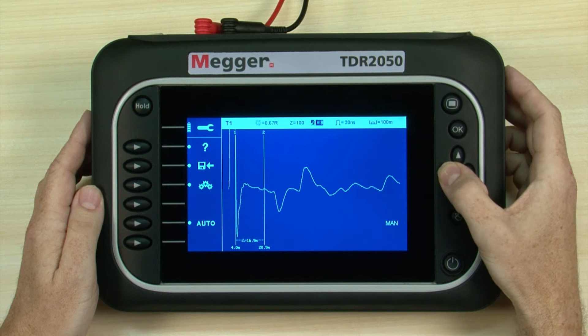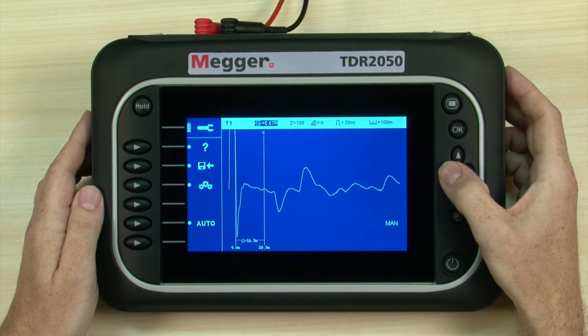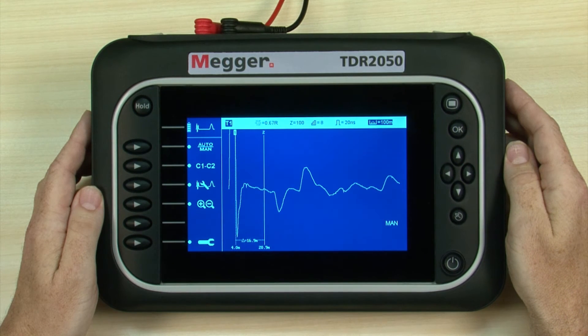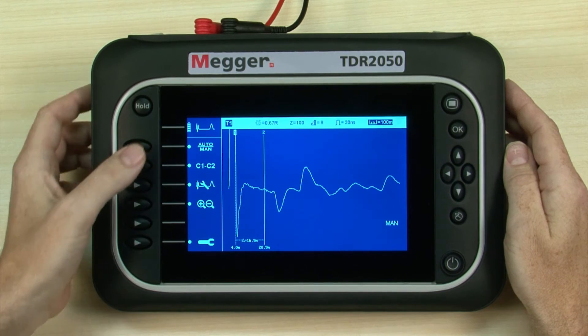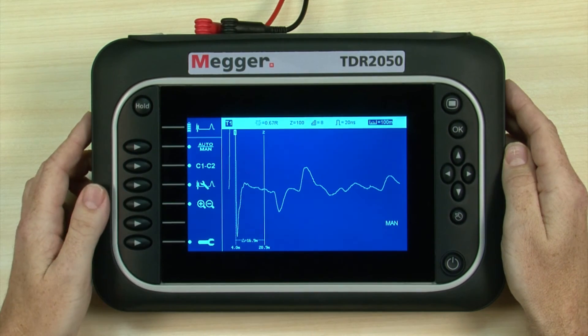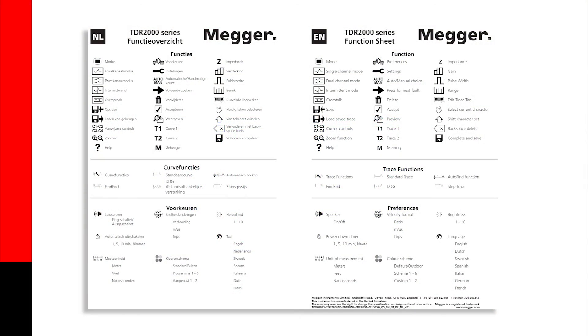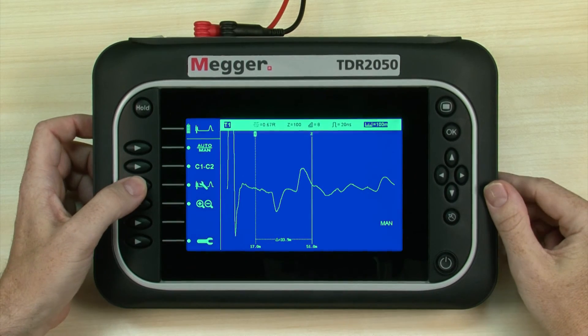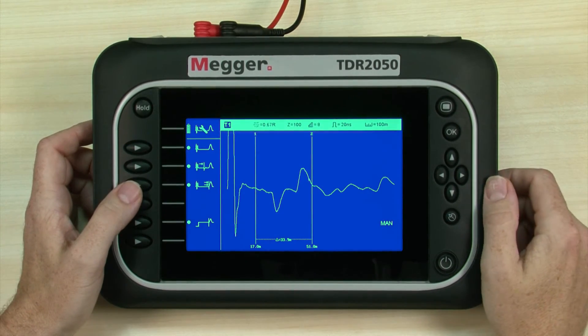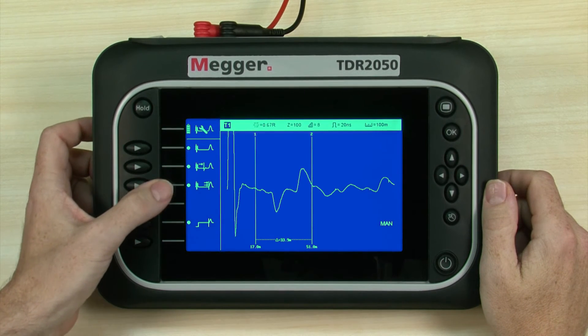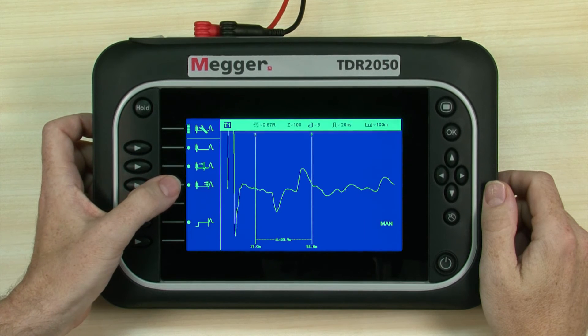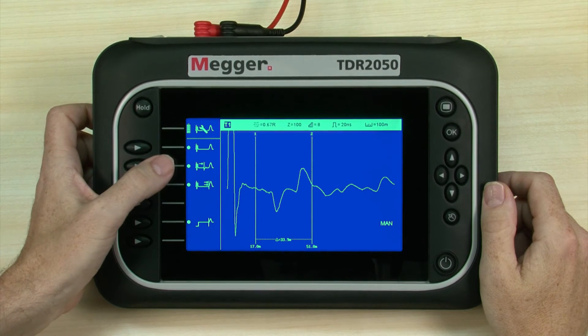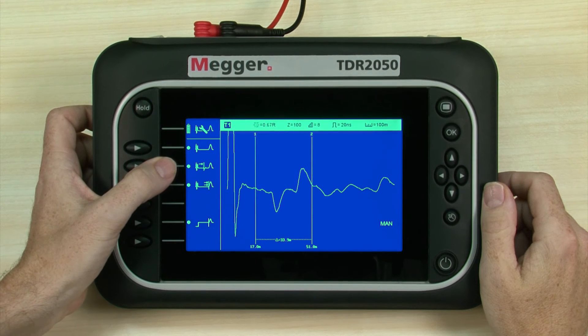Left and right navigation buttons highlight a specific parameter. The back button can be used at any time to return to the previous screen. Menu icons identify individual functions or group of functions. For those who like a crib sheet, we supply a full list of icons and functions on the printed function sheet. We need to select the trace functions menu. Here we can see a list of functions available for our chosen settings. Find End automatically determines the end of the cable, useful for fast measurement of cable length. Auto Find allows us to jump directly to a detected event.